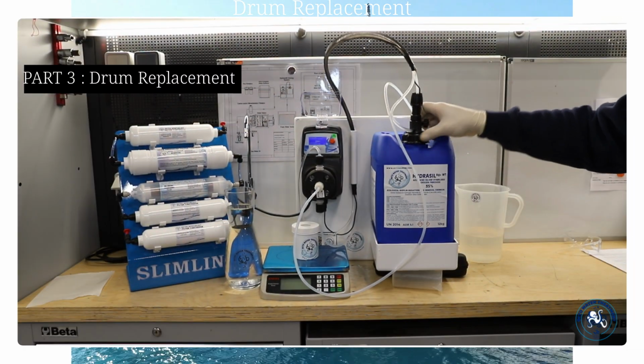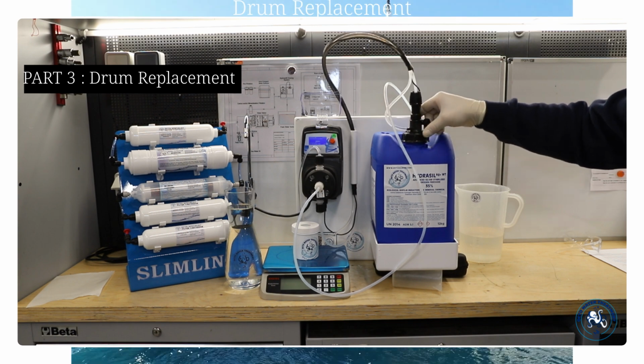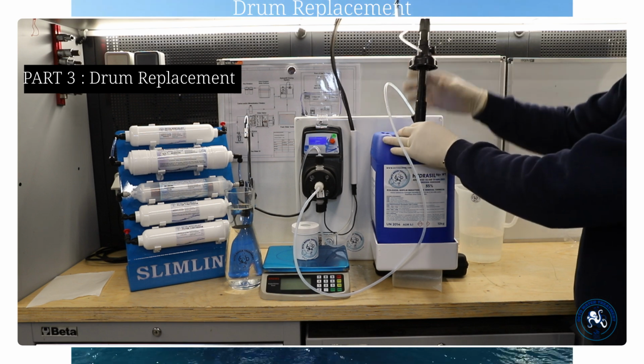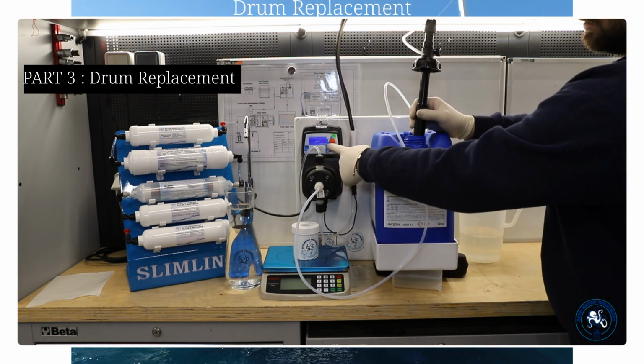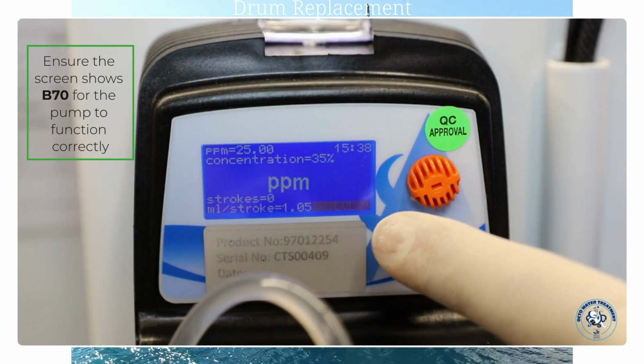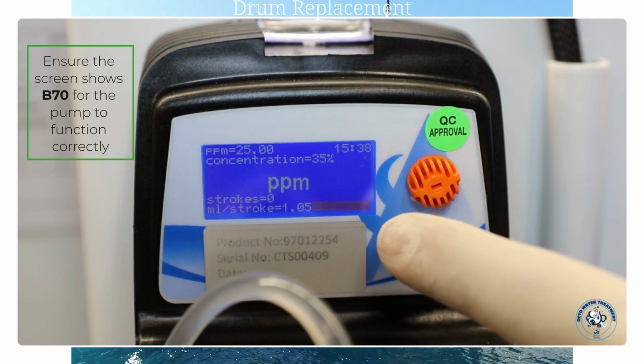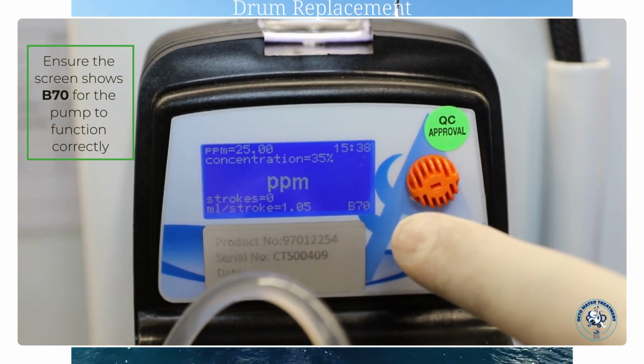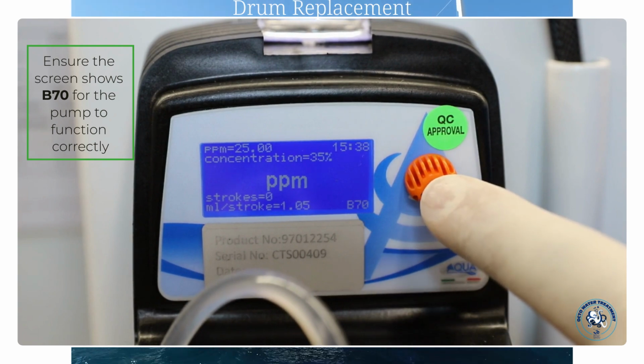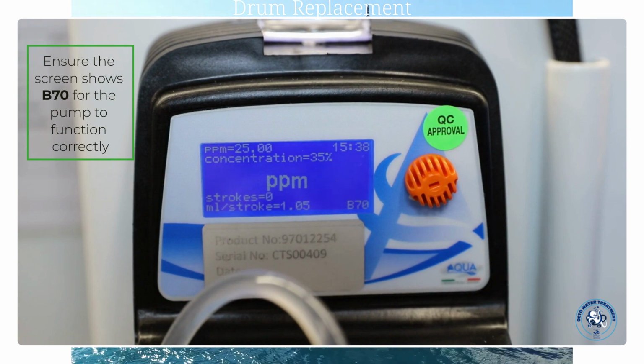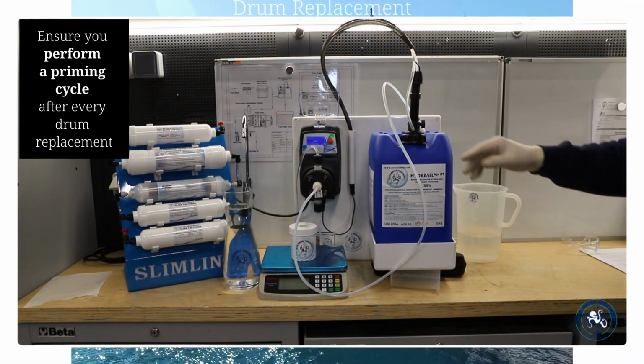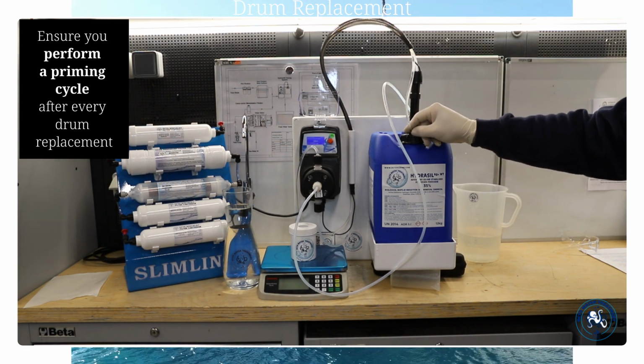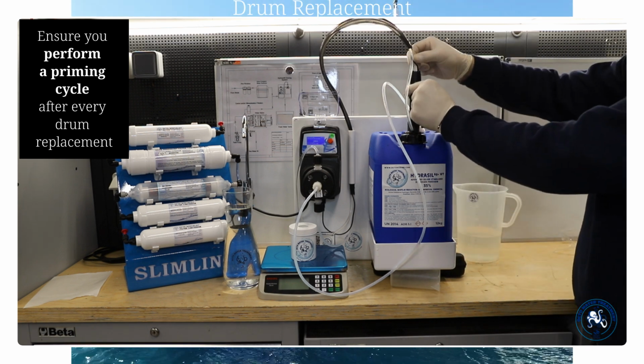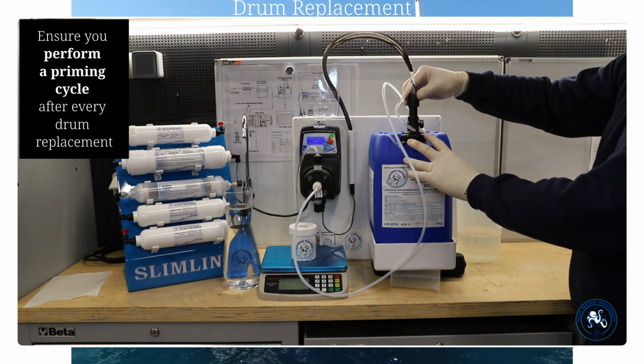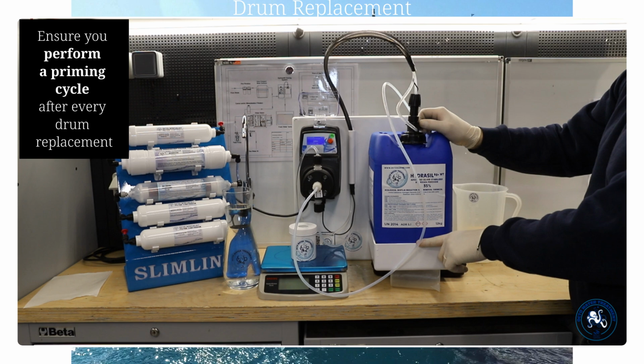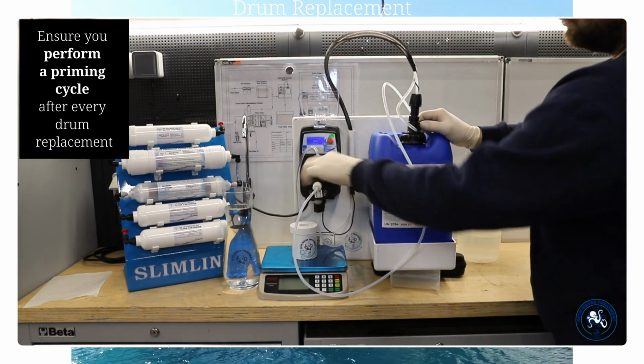Lastly, when the drum is empty and the level is low, there will be an alarm at the bottom right-hand side of your screen. The alarm flashes level. You just need to change the drum and the alarm should disappear. If it doesn't disappear, hold the button down. It will return to B70 and you are ready to go. When you have replaced the new drum, remember to double-check the tubes are not pinched and you have inserted the wand to its lowest point, so it can suck up the liquid effectively. Check all the nut connectors are tightened correctly. And very importantly, ensure you perform a priming cycle after every drum replacement.